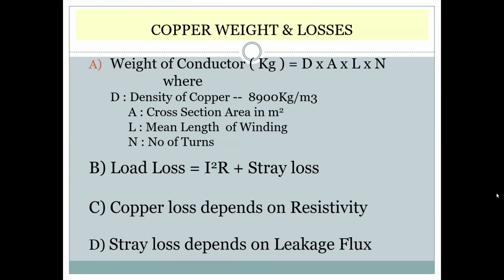Next. Weight of conductor, we can find out from the density of copper, which is standard, the cross section, and the number of turns. Load loss is I squared R plus stray loss, these are together. Copper loss depends on resistivity, stray loss depends on leakage flux. This we have already covered. So these are the basic design parameters we have to consider while designing a transformer. Next.